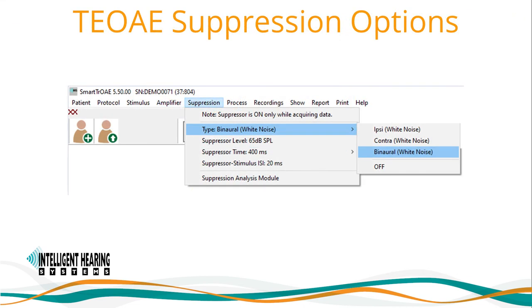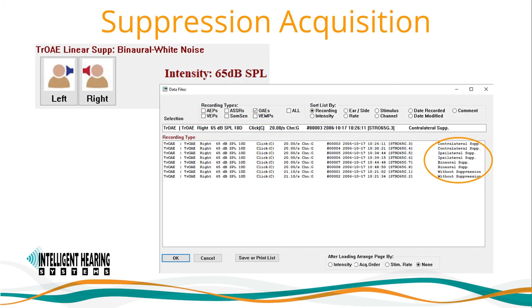There are four suppression options: no suppression or baseline; contralateral suppression, where the masker signal is delivered to the opposite ear from the one being tested; ipsilateral suppression, when the masker signal is delivered to the same ear being tested; and binaural suppression, where the masker signal is delivered to both ears. Per Berlin and colleagues, binaural masking noise is most effective in suppressing otoacoustic emissions. Once the parameters are set, click right or left on the main screen to acquire the data. IHS recommends right-clicking on the time domain waveform and adding a comment with the type of suppression used — this comment will appear in the load recordings display window and ease file selection during comparison and analysis.